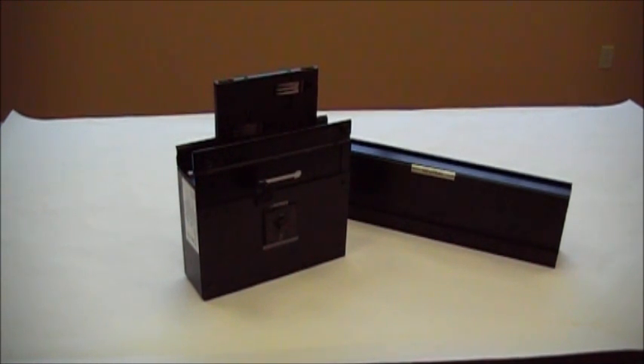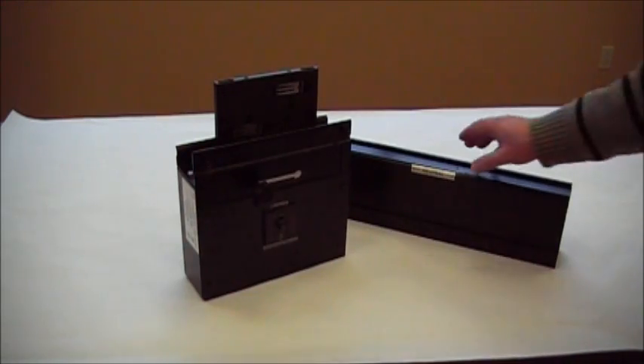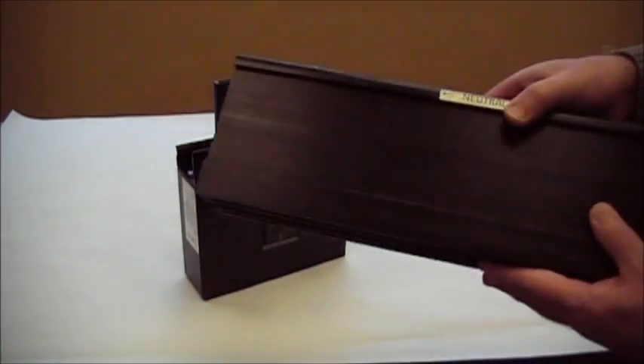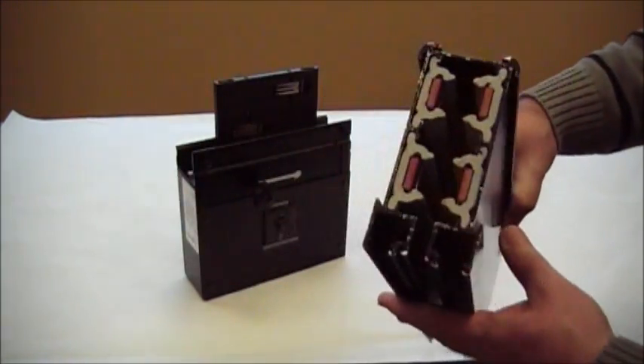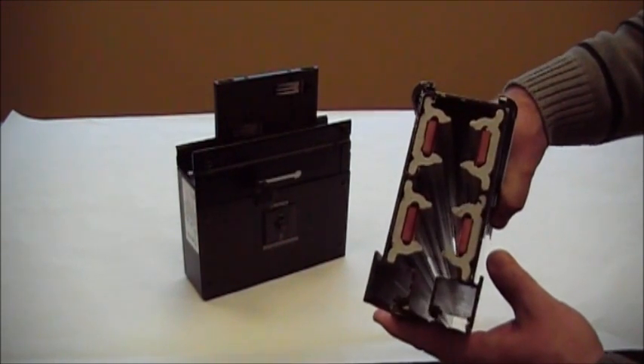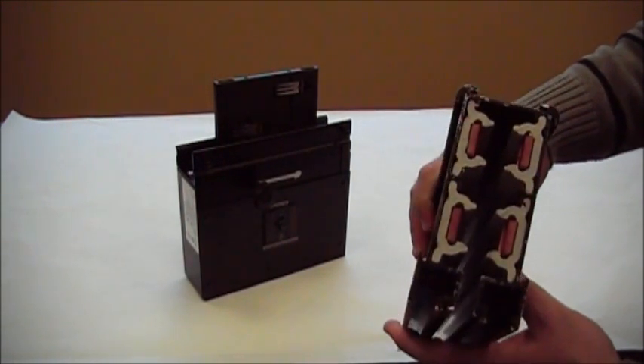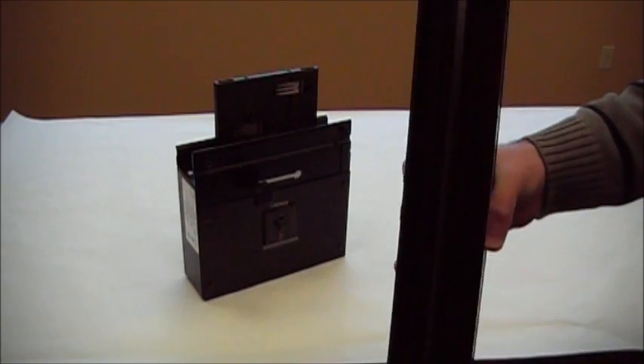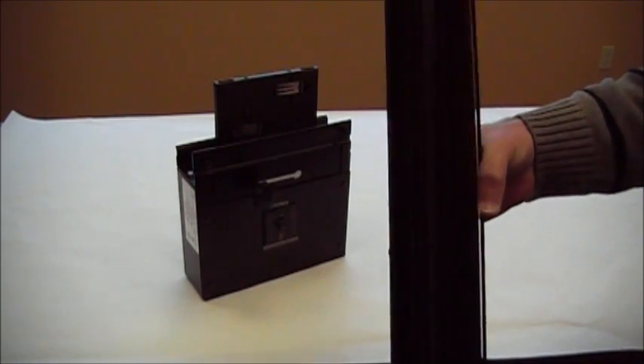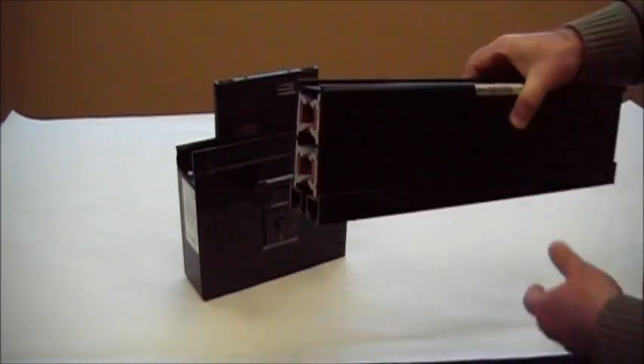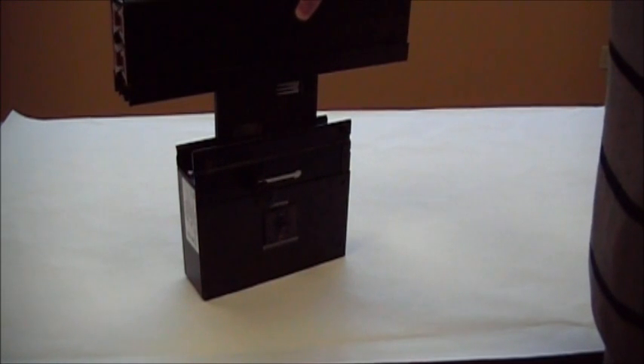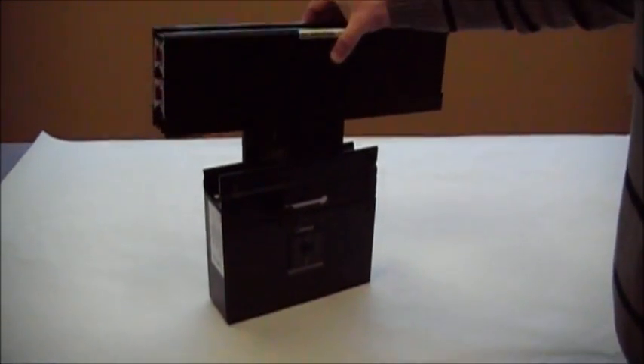Today we have the PDI Power Wave bus system, and we will demonstrate the insertion of a plug-in unit into the busway. The power bus is an aluminum housing. It has 4 copper conductors. They're flat bars that run the length of the housing with a continuous access slot on the bottom. The paddle of the plug would be inserted up into the mounted busway system.